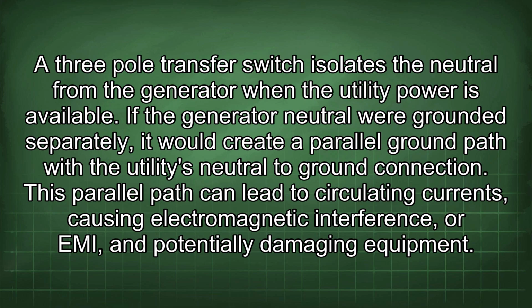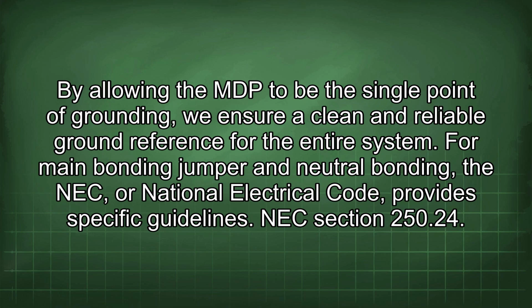connection. This parallel path can lead to circulating currents, causing electromagnetic interference, or EMI, and potentially damaging equipment. By allowing the MDP to be the single point of grounding, we ensure a clean and reliable ground reference for the entire system. For main bonding jumper and neutral bonding, the NEC, or National Electrical Code, provides specific guidelines.